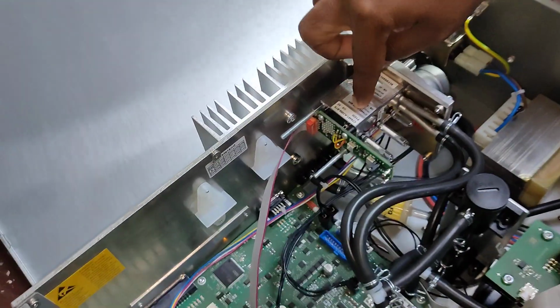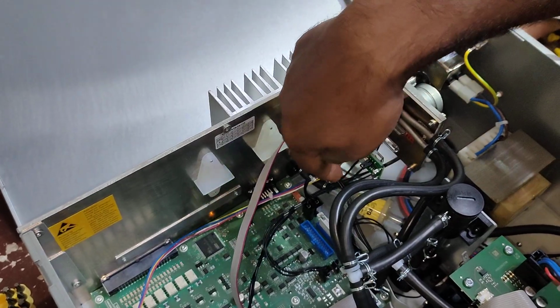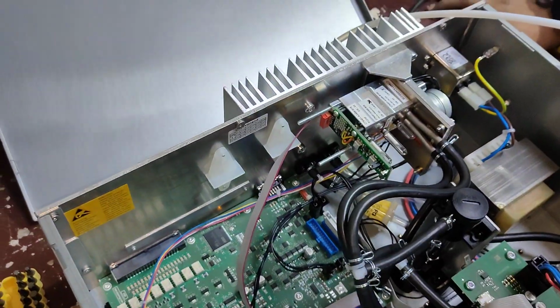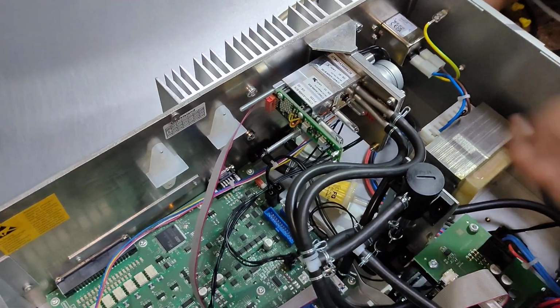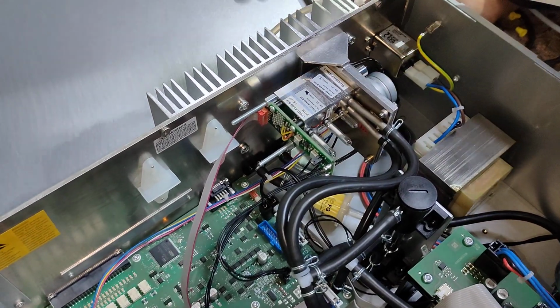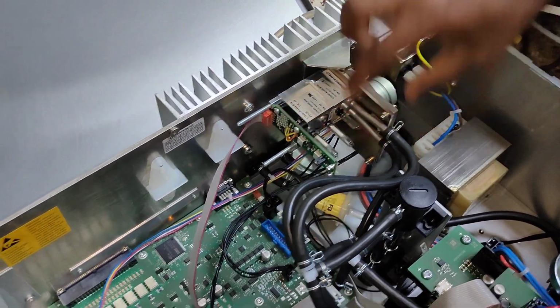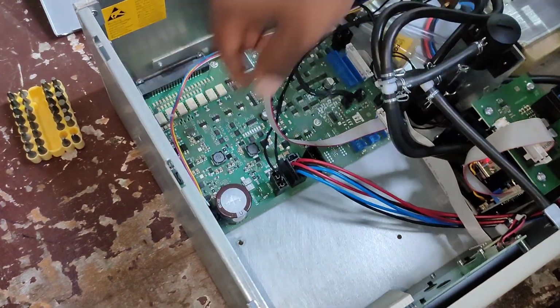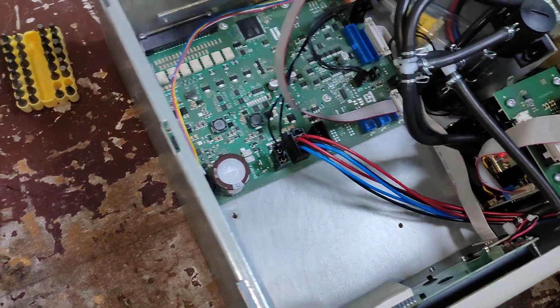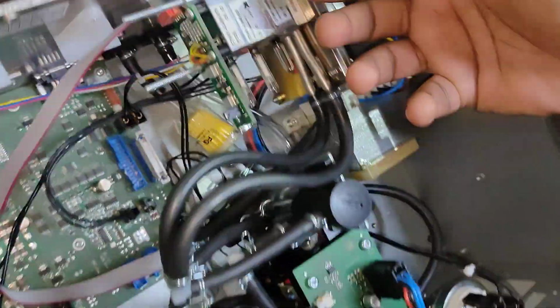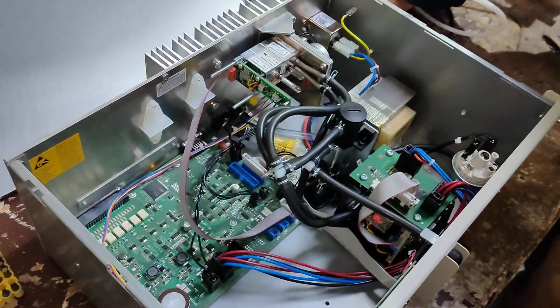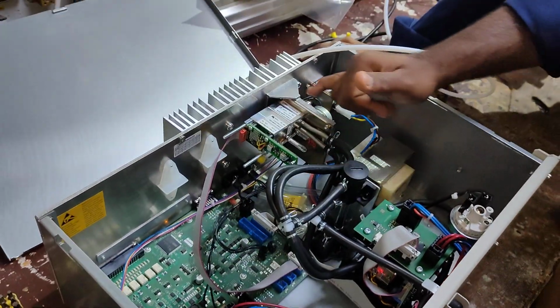Similarly for CO, you can remove these 2 screws and pull the detector back. Whenever you are replacing the detector, you have to first remove all these tubes, 1, 2. Remove the IR source, chopper motor, detector. This is your detector cable. And then there are 3 screws here behind. It is holding this whole panel. So 1, 2, 3. If you remove those 3 screws, this whole body will come out. Only for CO. And then you can replace the detector or your IR source.